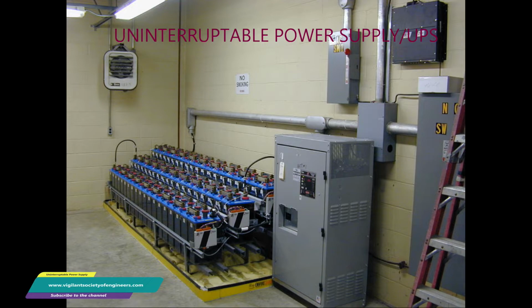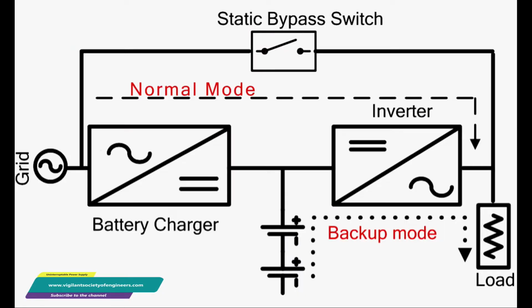There will be a number of limiting factors depending upon the application. Batteries can be discharged at a lower level should the design call for a shorter autonomy, as in the case of emergency lighting, where there is a requirement for a long autonomy. Therefore, the condition helps to allow the maximum design life of the battery. So the amount of current delivered to the load, in time and minutes, would be the autonomy of the battery.